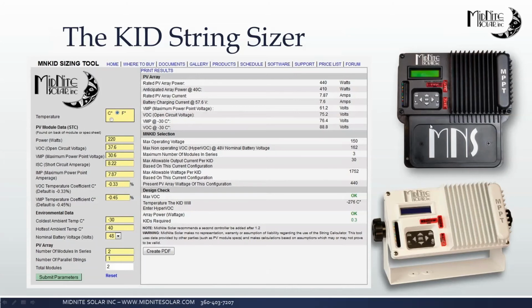So the string sizing tool for the Kid, if you've played with the one for the Classic, they're quite similar. The Kid is 30 amps into the battery, period. So if it's on a 12-volt battery, that's going to be like 500 watts. If it's on a 24, that's like 1,000 watts. So essentially, on the string sizing tools over here on the left in these yellow boxes, you're going to input your data, the wattage of the module you want to use, Fahrenheit or Celsius up here. The temperature correction coefficients, if you're not 100% sure on the modules, the defaults are going to be pretty close for any module out there. And then you get to play around down here.